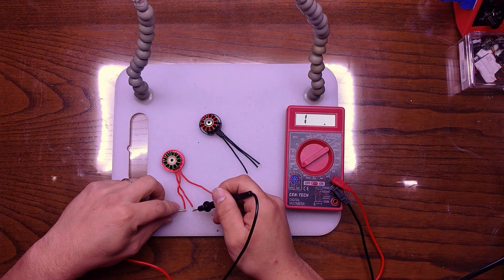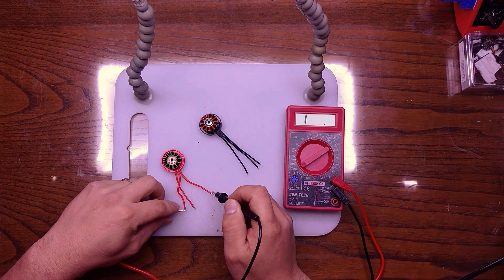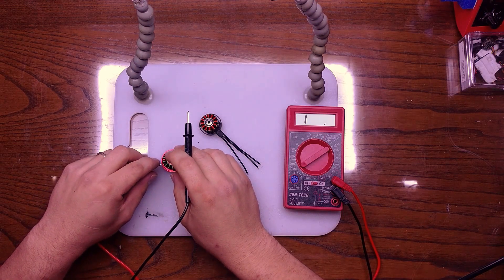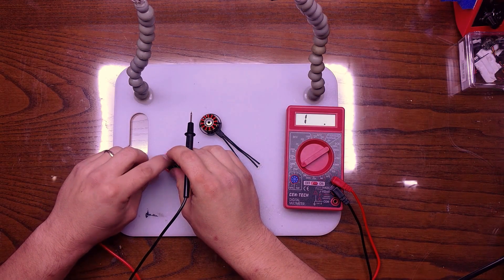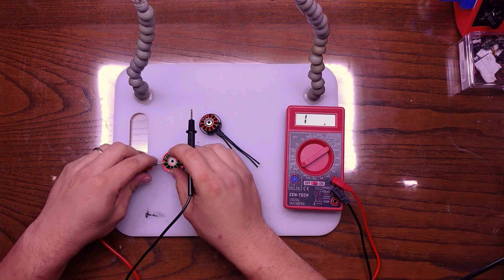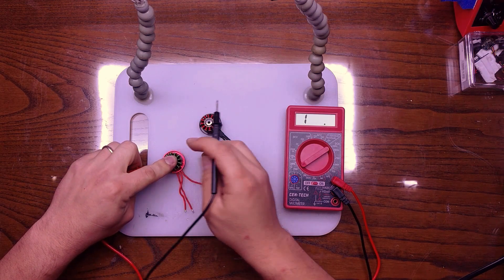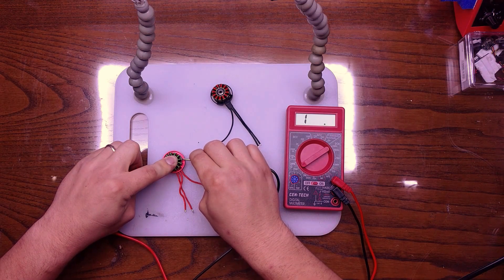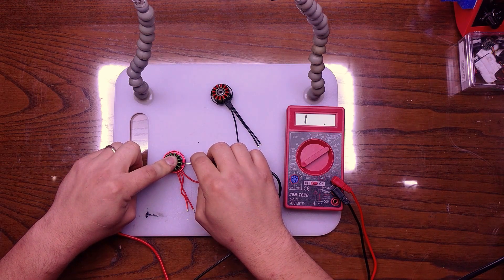As you can see, all these leads already have continuity because of the way that we've wound it. So what I'm going to do right now is make sure that I have a connection. I just hold it down with my finger and you want to see if you have a connection from your stator to your leads.